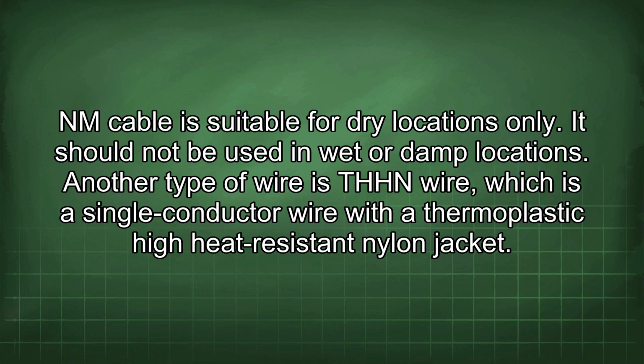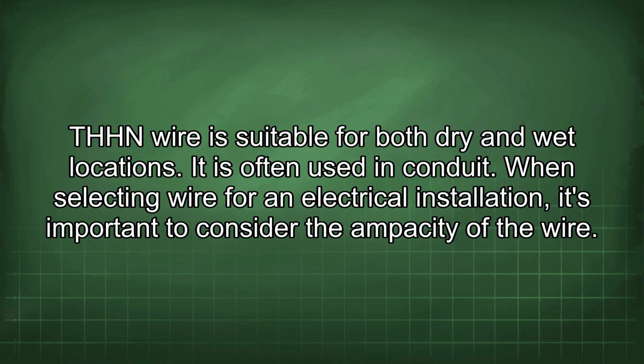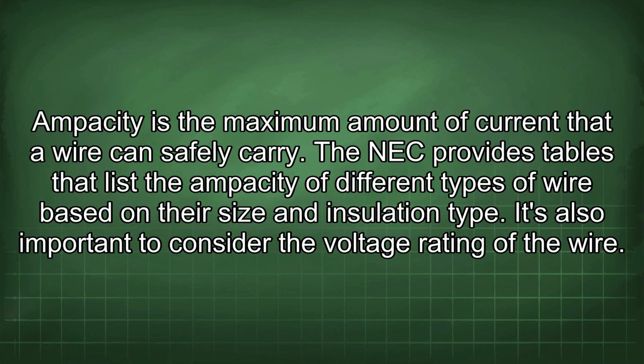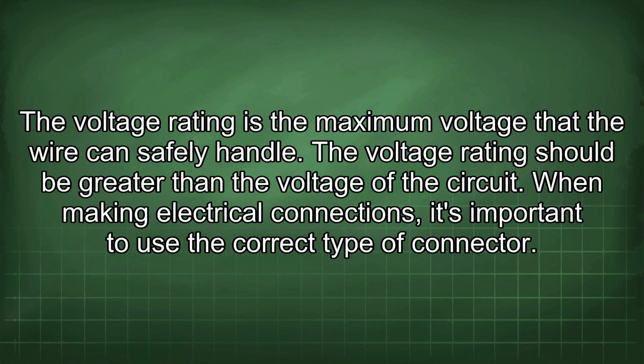Another type of wire is THHN wire, which is a single conductor wire with a thermoplastic high heat resistant nylon jacket. THHN wire is suitable for both dry and wet locations. It is often used in conduit. When selecting wire for an electrical installation, it's important to consider the ampacity of the wire. Ampacity is the maximum amount of current that a wire can safely carry. The NEC provides tables that list the ampacity of different types of wire based on their size and insulation type. It's also important to consider the voltage rating of the wire. The voltage rating is the maximum voltage that the wire can safely handle. The voltage rating should be greater than the voltage of the circuit.